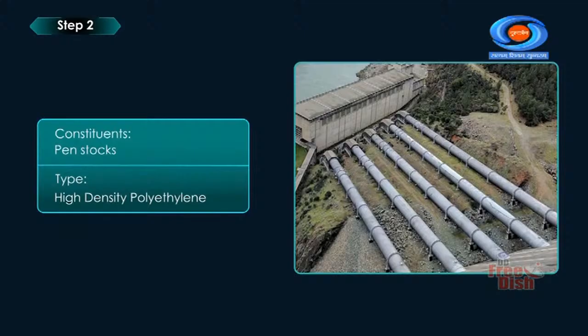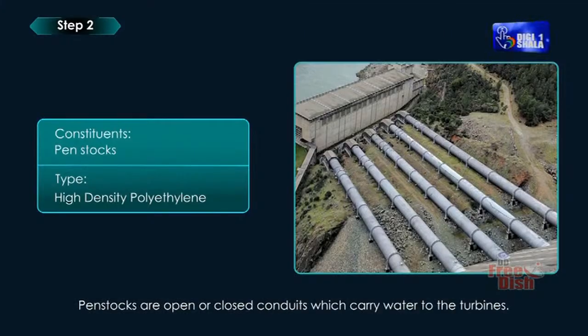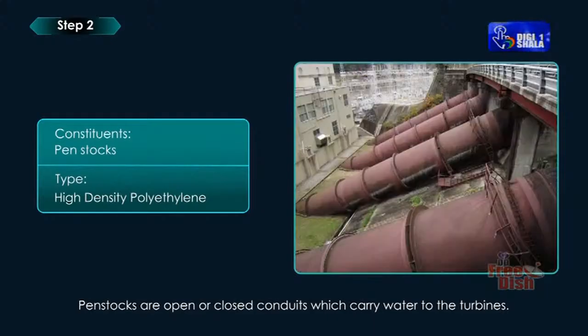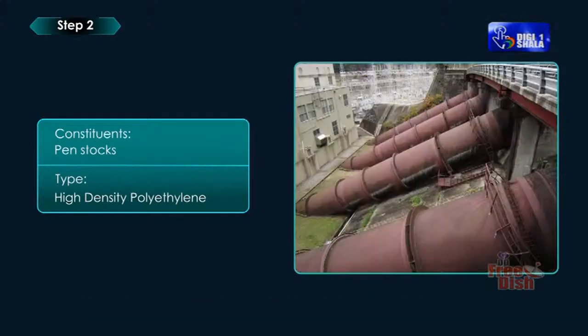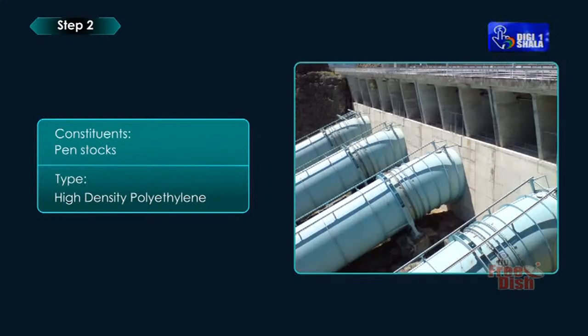Type: high density polythene. Function: penstocks are open or closed conduits which carry water to the turbines. They are generally made of reinforced concrete or steel. The thickness of the penstock increases with the head or working pressure. Various devices such as automatic butterfly valve, air valve, and surge tank are provided for the protection of penstock.